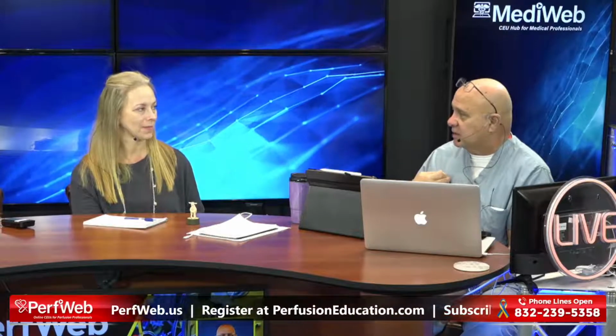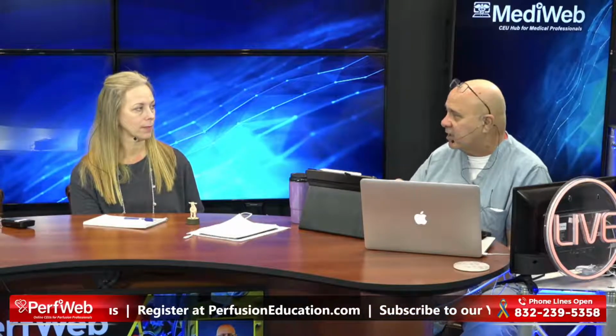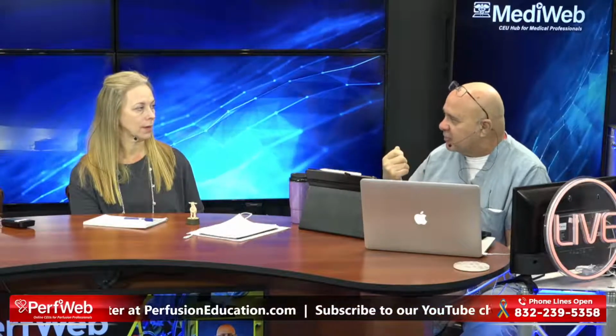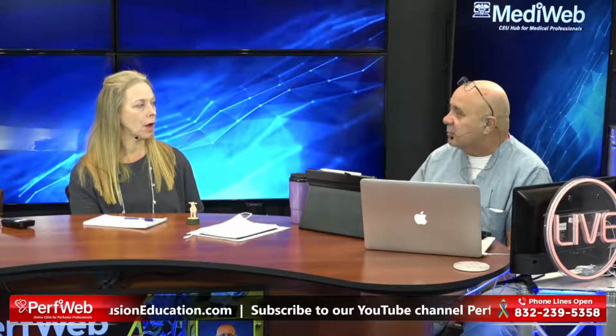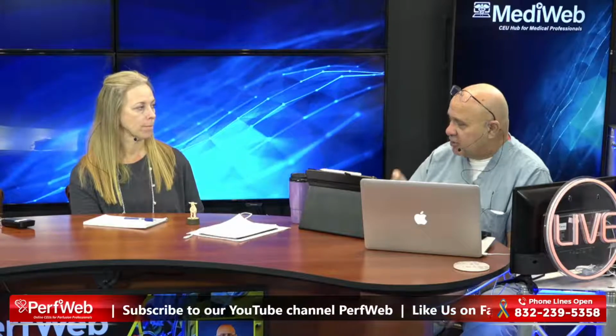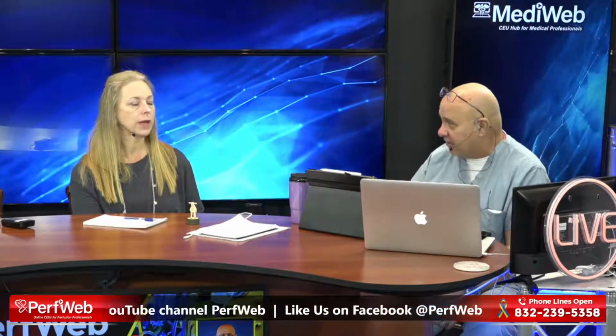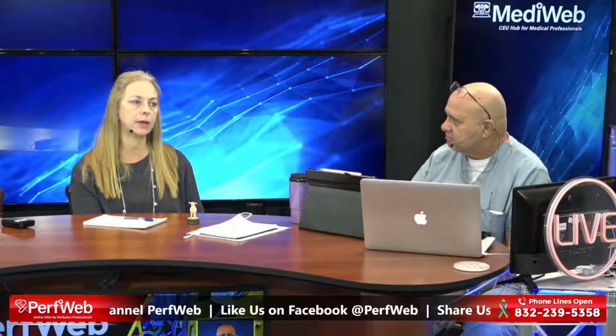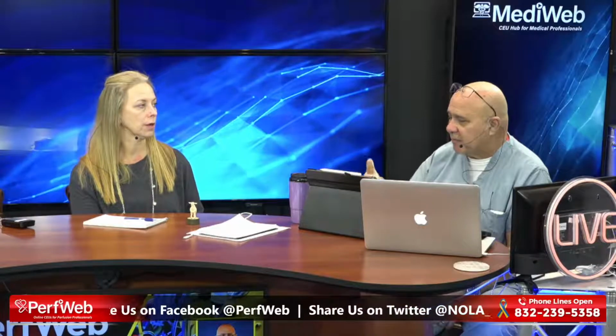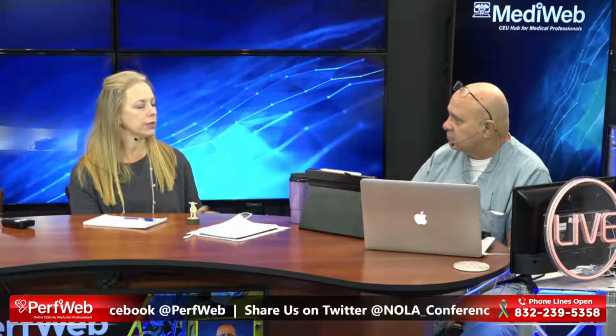I do that still to this day. In fact, I take it off and I still breathe the gas. I always make sure I do it distal to the filter, because that filter can crack as well. Yes, it needs to be distal to your filter, right before your oxygenator. Correct. You can just take it off and put your finger over the hole. Yeah, you can do that.